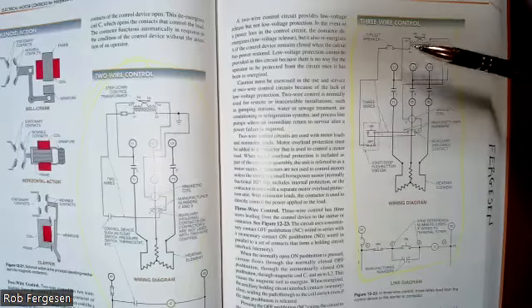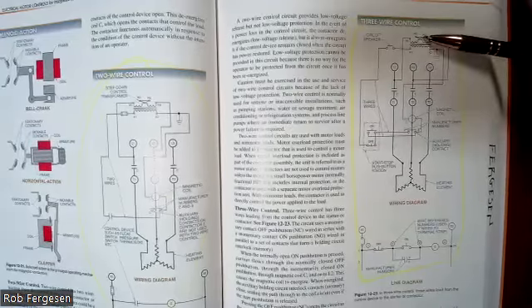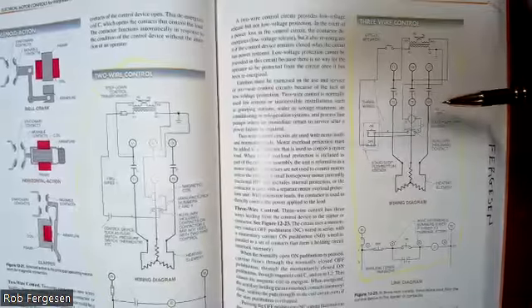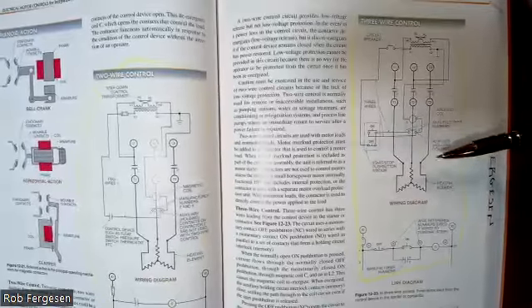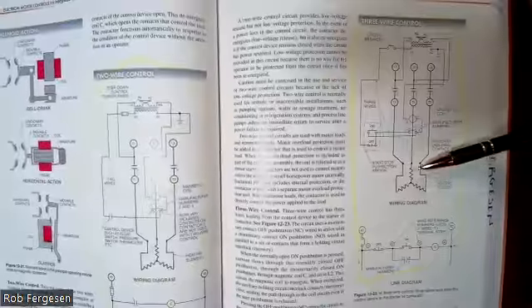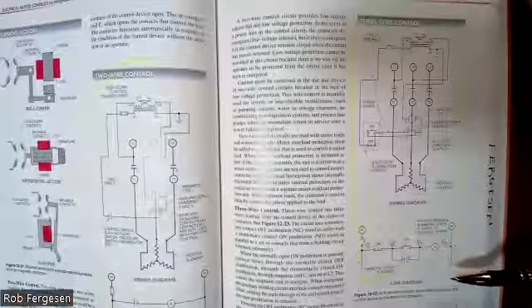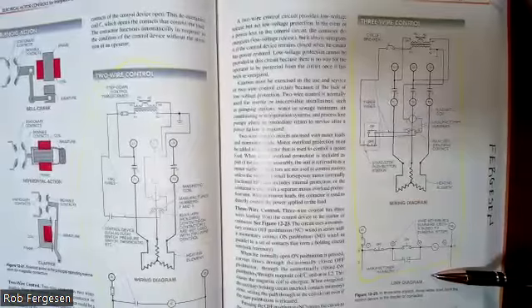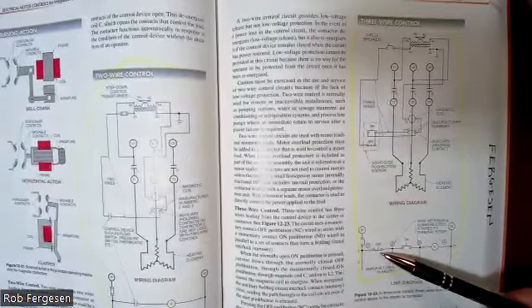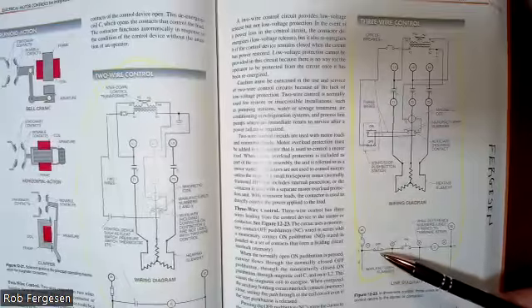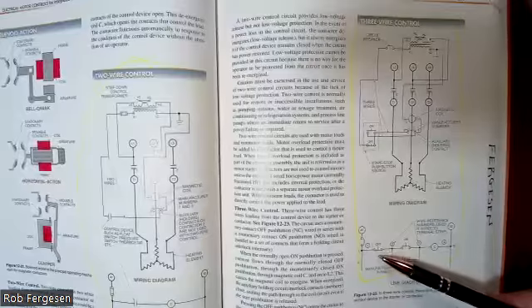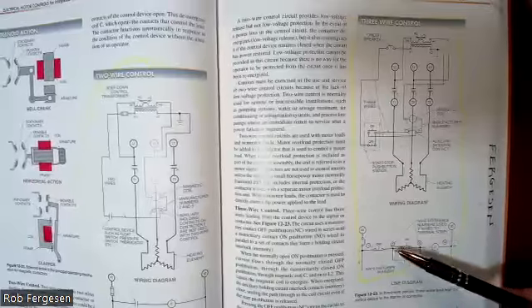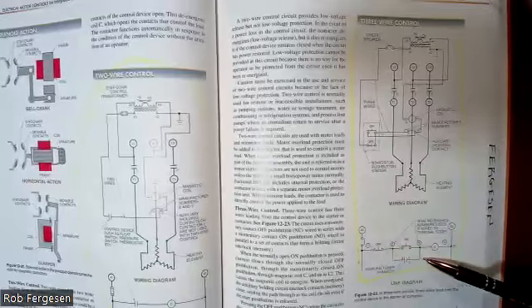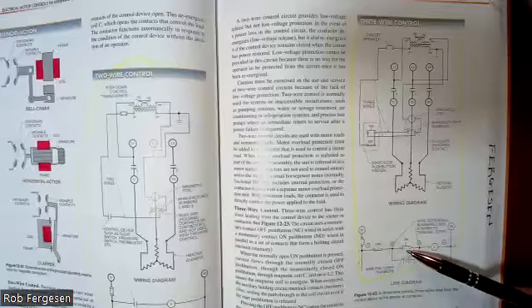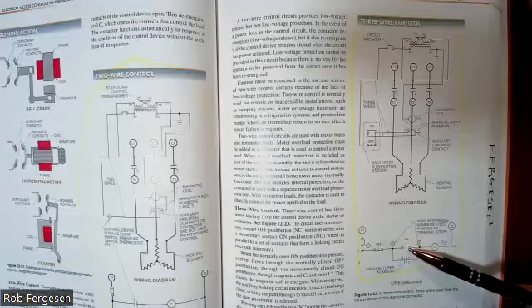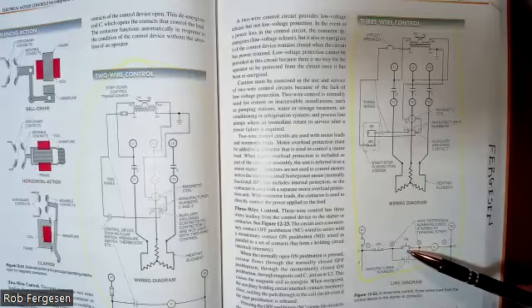Number 1, you see your lines in, you see your control transformer, same as last time. You see your T1, T2, and T3 leading to your, in this case, heating element, but it easily could be a motor. And down here, we see our control diagram, the line diagram. We almost always, in a manual situation like this, have a normally closed off push button, which means when it's not being pressed, it's closed. And that's attached to a circuit that has 2 paths. One path goes through a normally open on push button, right?